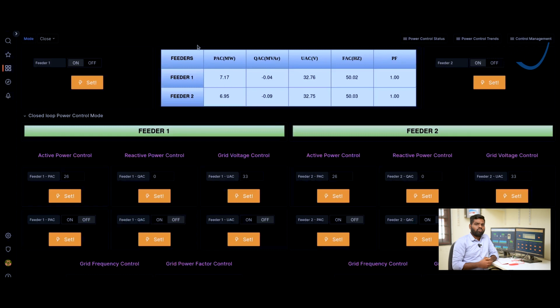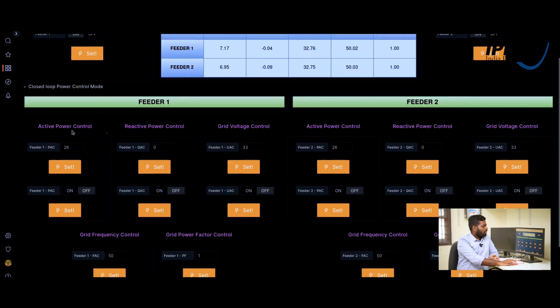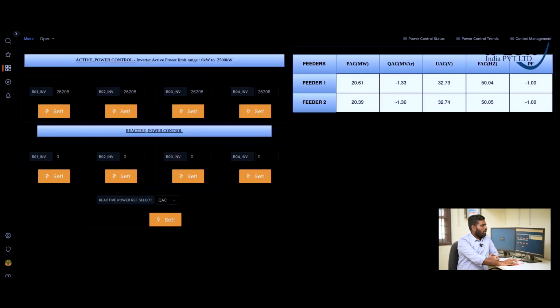This is the power control overview screen, and this is the closed loop set point. Here the operator can set the set point limit. In closed loop control, whatever set point limit the operator sets, with the feedback from the energy meter, is controlled by our logic, which will run through the control set limits. Here the active power control set point, reactive power control set point, voltage control, similar to feeder 2 also. And then these are the open loop control set point limits.